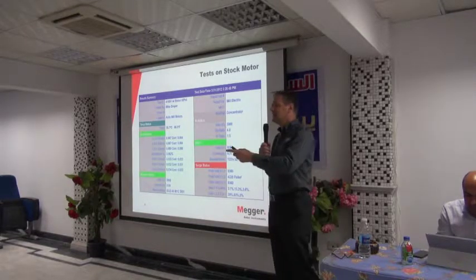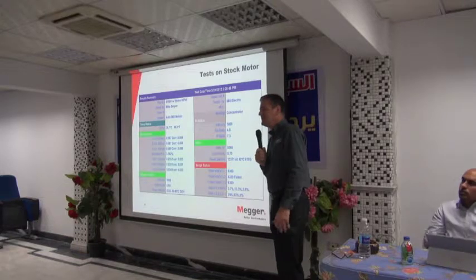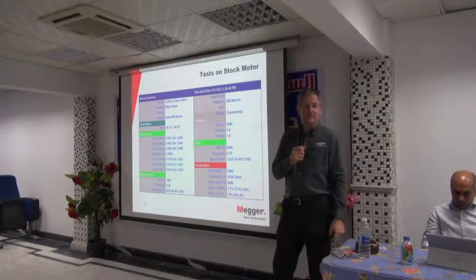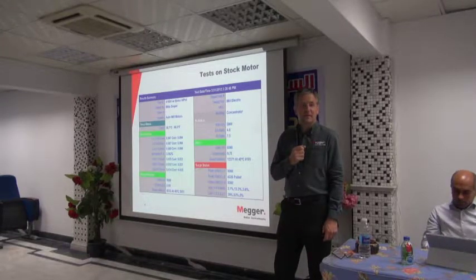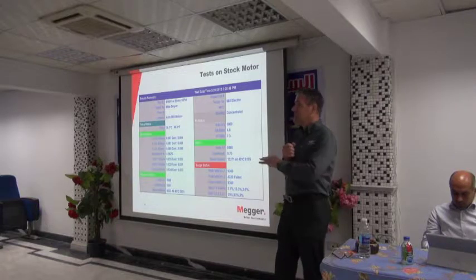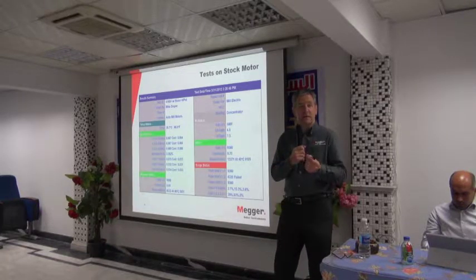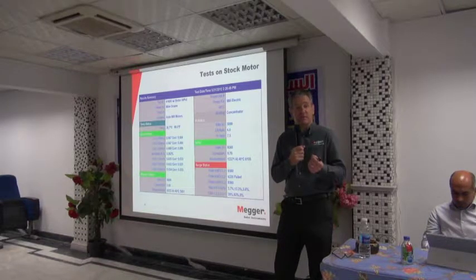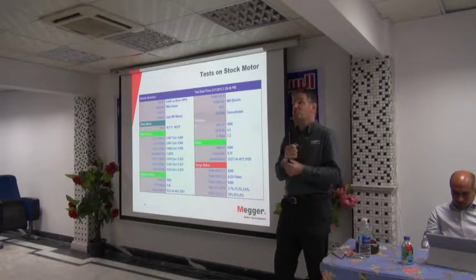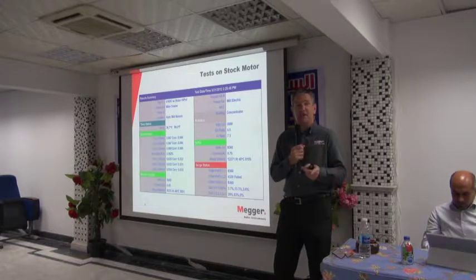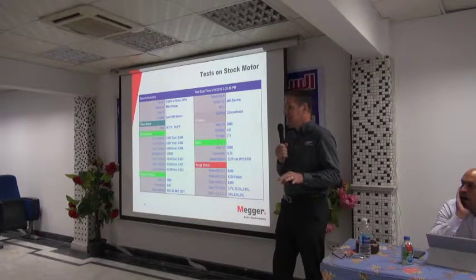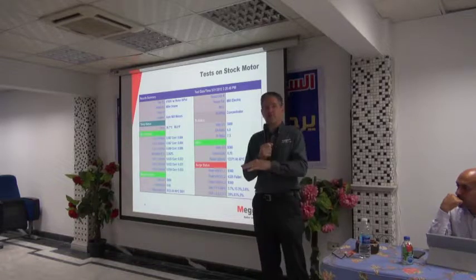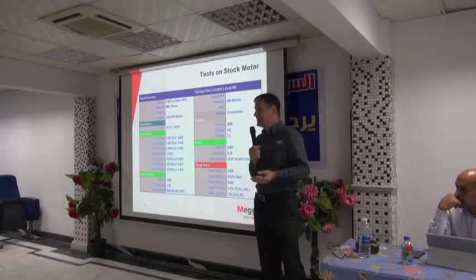What did we calculate yesterday? It was for 2 months. It was 1 million. £1 million or dollars. $1 million. Okay, not every motor is like this, but this gives you the understanding of the importance of reliability testing. We can find these problems that are coming that will cause your motor to fail before they fail, and you can make a plan to change the motor at the most convenient time. Okay, so that's static testing. I hope that was interesting. We have a break and then we'll talk after the break about dynamic testing.